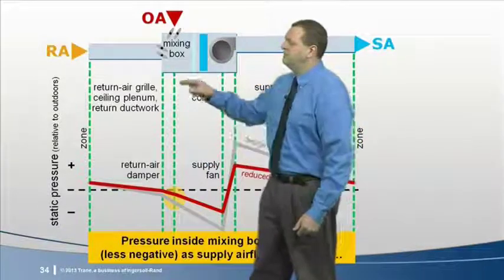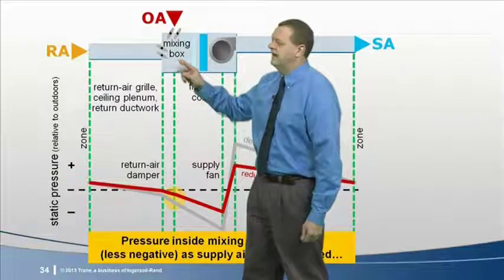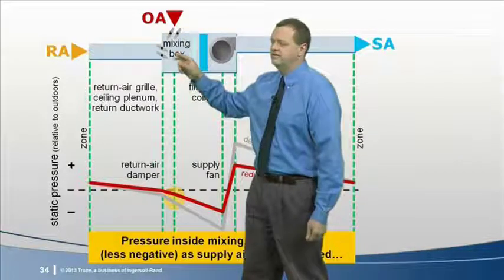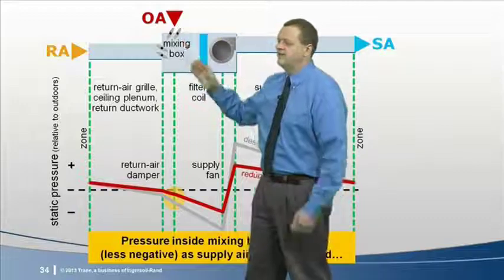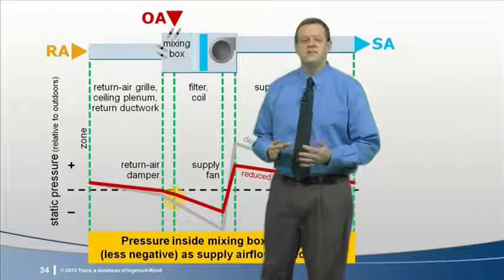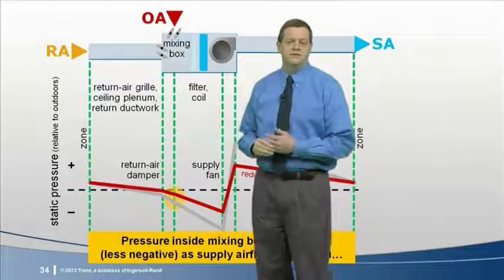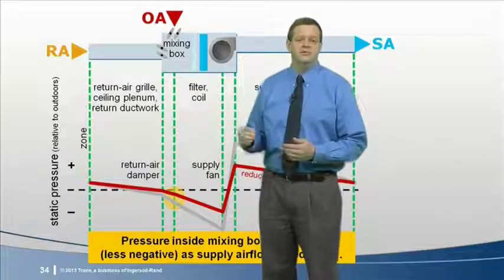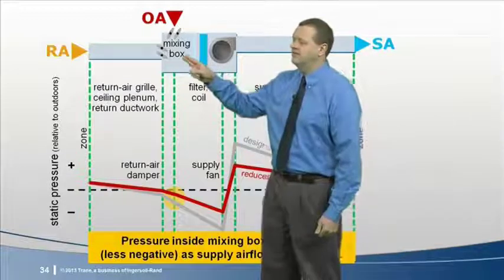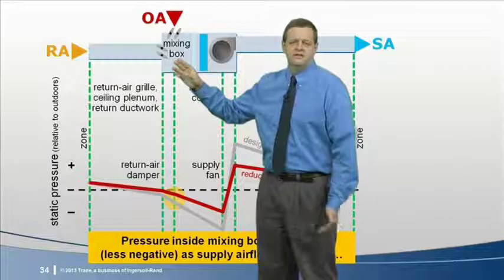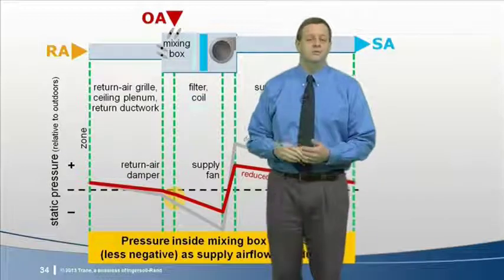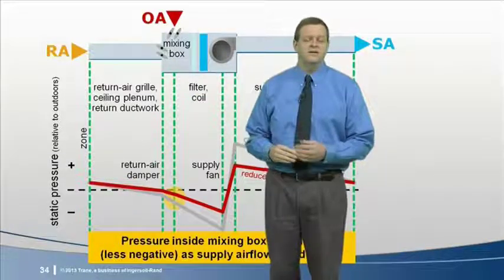The static pressure inside this box has a direct effect on how much outdoor air enters the system. If this damper remains set at a fixed position, the CFM of outdoor air entering through the damper will decrease because the pressure inside this mixing box is not as negative. The result is that outdoor airflow will decrease as supply airflow is reduced.